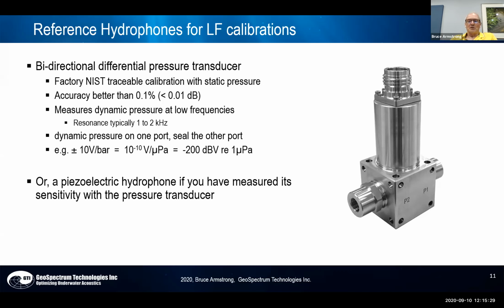Now, the pressure transmitter is calibrated with static pressure, but it still works at low frequencies. It's got a resonance of 1 or 2 kilohertz, so you can use it at 1 hertz or 10 hertz or 100 hertz, it's fine. If you got up to 1 or 2 kilohertz, it would not be fine. So the way you use it is that you put the dynamic pressure inside the box on one port, and you seal the other port by some means.